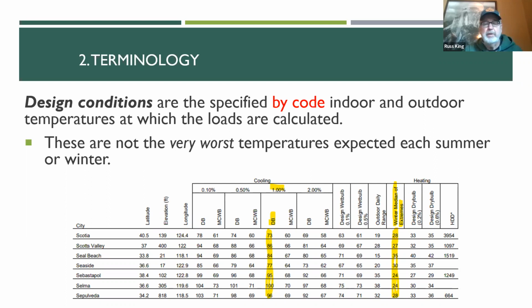So here's some examples here. There's this huge table that's specified by code. It has all the cities in California. If you're not within a city zone or within the city boundaries, you'll pick the closest city. And if you are not within a city and you might be in a microclimate, you are allowed to adjust the temperatures, but you have to get permission from the local jurisdiction to do that. Okay.